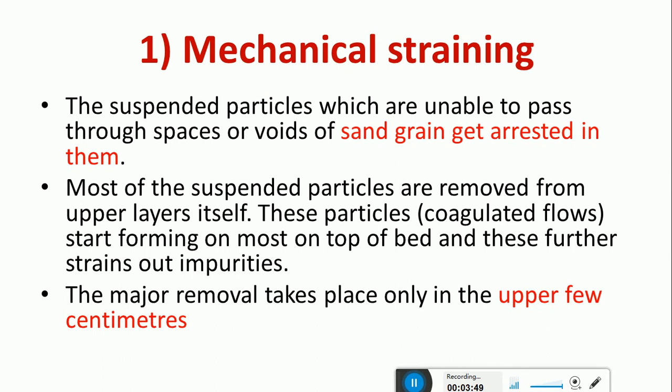Okay. So let us see in detail what mechanical straining is. Here the suspended particles which are unable to pass through the spaces or voids of the sand grains get arrested in them. When you pass the water through the sand particles, there will be small void spaces present between the sand particles. These act as the strainer media. So the particles get trapped in the spaces between the sand grains, and hence because of this mechanical straining the filtration takes place.